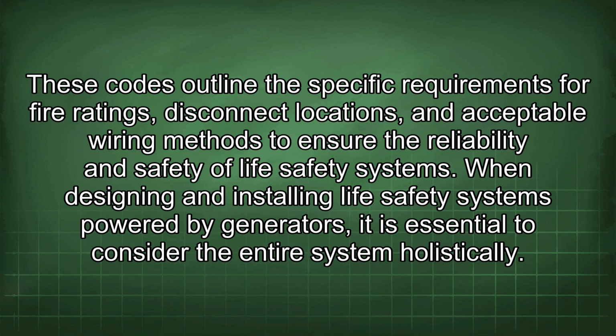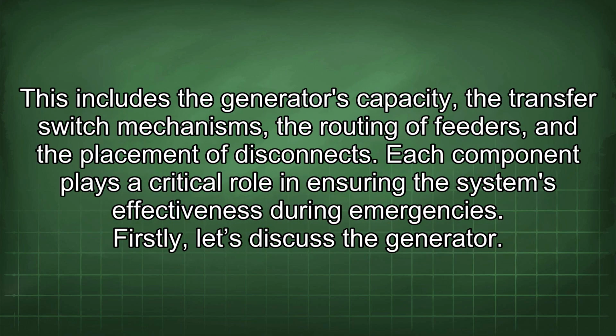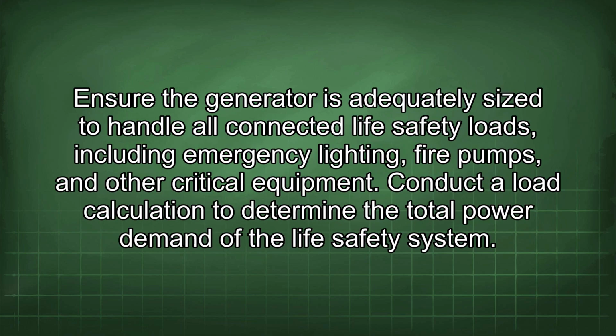When designing and installing life safety systems powered by generators, it is essential to consider the entire system holistically. This includes the generator's capacity, the transfer switch mechanisms, the routing of feeders, and the placement of disconnects. Each component plays a critical role in ensuring the system's effectiveness during emergencies. Firstly, let's discuss the generator. Ensure the generator is adequately sized to handle all connected life safety loads, including emergency lighting, fire pumps, and other critical equipment. Conduct a load calculation to determine the total power demand of the life safety system.